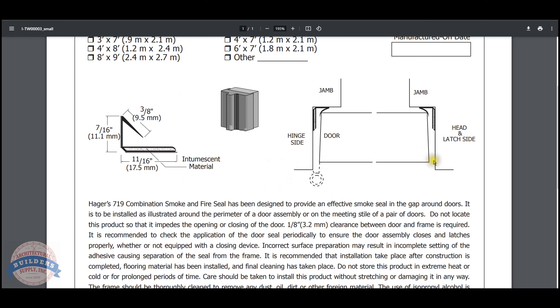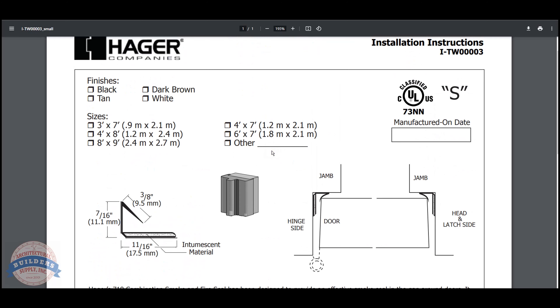So if you've got less than an eighth-of-an-inch, you probably don't need this to begin with, and it would not be the proper material to use because you don't have the margin required to fit it in where it has to go. If you've got beveled-edge doors, that's going to really help, but you have to have that eighth-of-an-inch, because when this corner is rotated around to the jamb, it's going to be awfully close. So you need that three-degree relief so it doesn't hit the intumescent itself.